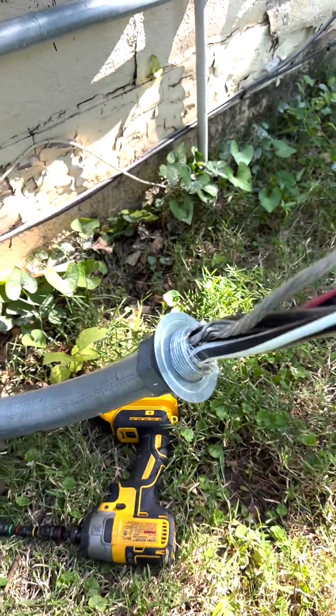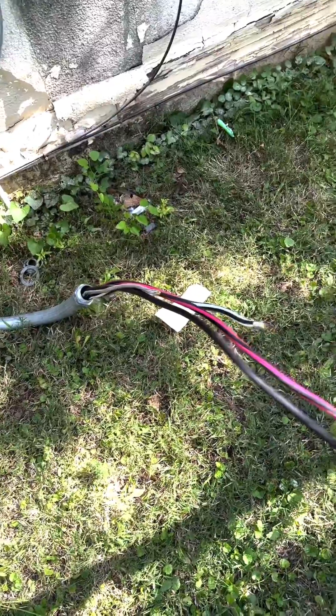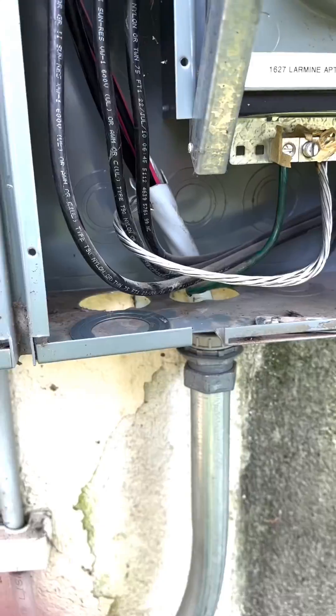When that happened, it kind of nicked the wires, so I had to inspect all of that and make sure everything was good to go. Otherwise I would have had to replace the wires, but honestly there were some dinged-up spots — one needed taped — but I still couldn't see any of the conductor. So I was okay with just patching it with tape and putting it back together, because like I said, I didn't see any of the conductor. If I would have, I would have just swapped the wire out.